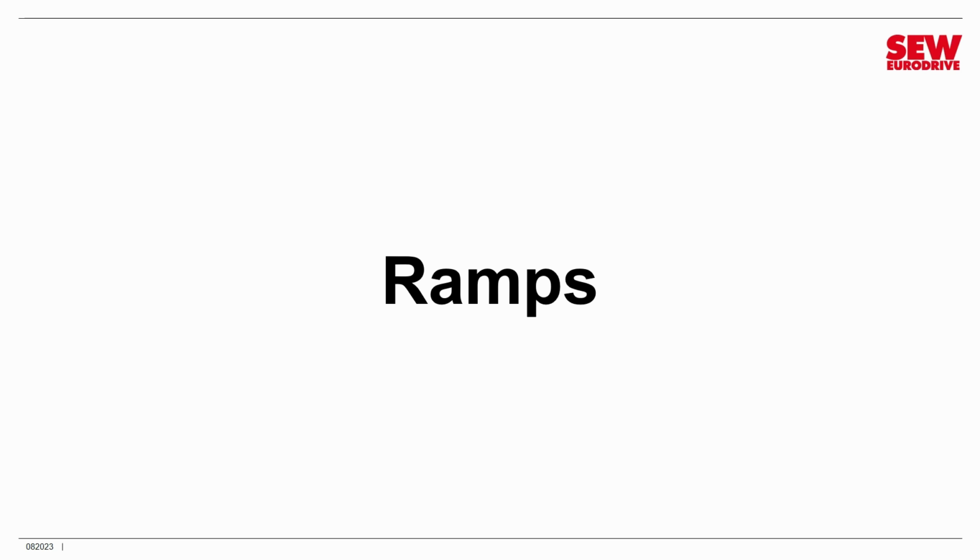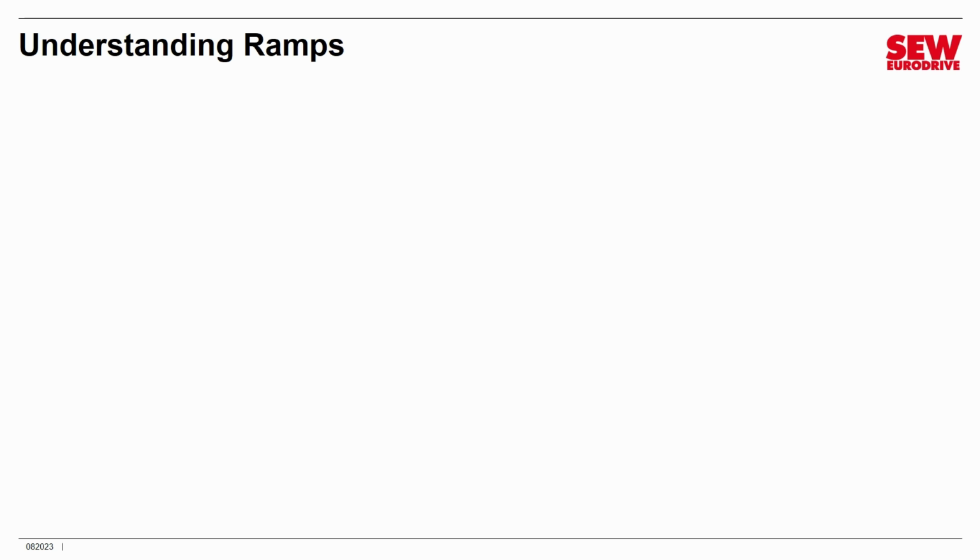Ramps are one of those things that you think should take about 30 seconds to explain, and then the more you get into it, the more you realize it's actually pretty sophisticated. So it's going to take a few minutes to cover ramps, but it's well worth it because ramps significantly affect how your VFD behaves and how it handles your application. So what is a ramp? Put very simply, a ramp is an acceleration or deceleration event.